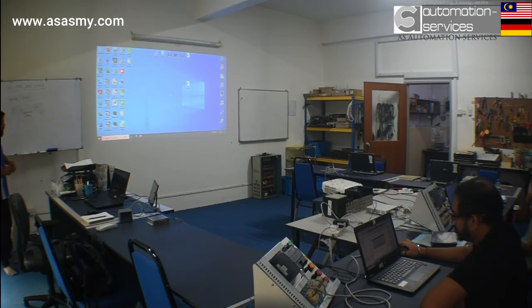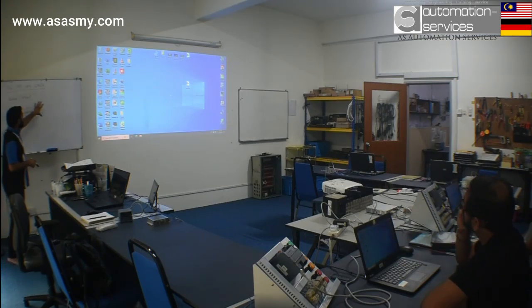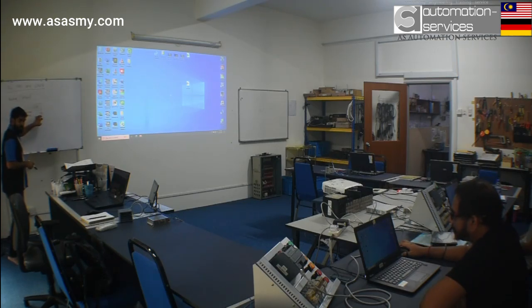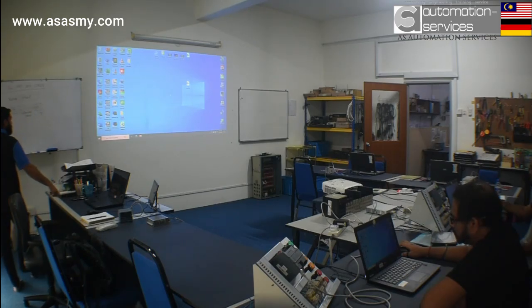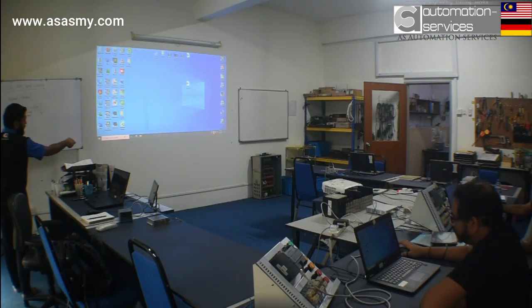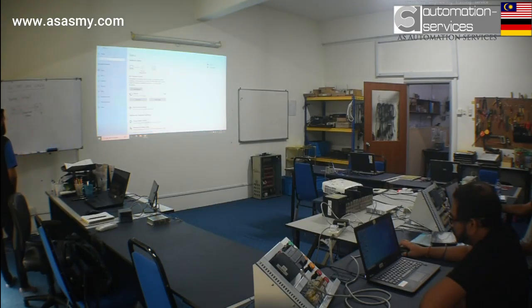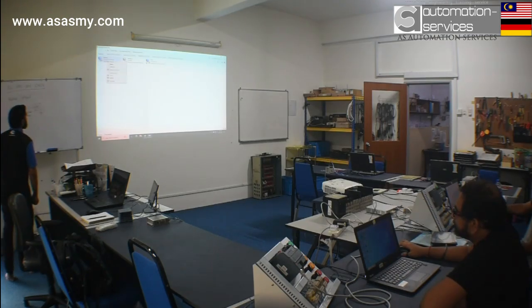Since we don't know the IP address of the PLC, what we do is set our PC to dynamic. Before that we check first whether it's already dynamic or static. So we right click the Ethernet, open Internet and network settings, go to change adapter options. Can you see Ethernet here? Right click, properties.